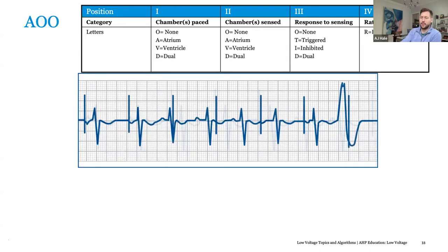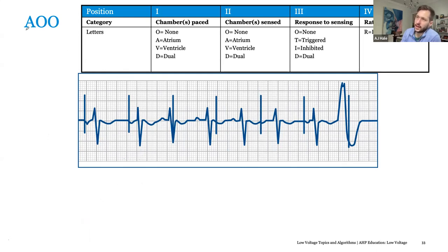So AOO, we talked about VOO. AOO is the same thing, it's just in the atrium. We talked about this last week, I believe, but we tend not to see atrial-based only devices. It was a thing in Europe for a while. The East Coast did it for a while.